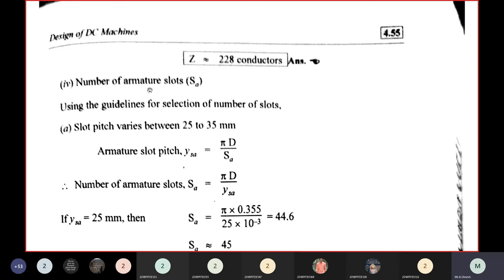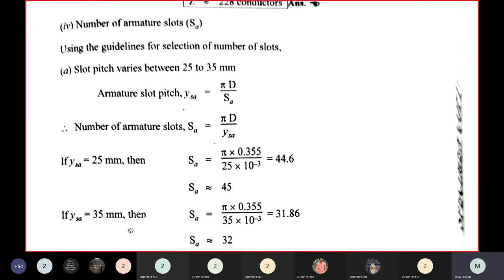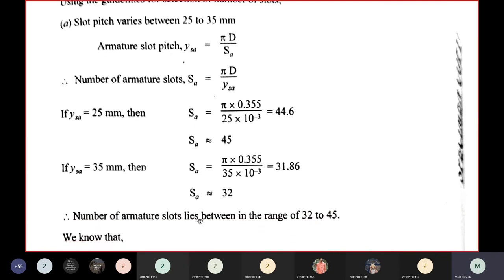Number of armature slots SA: slot pitch YSA = πD/SA. For YSA = 25 mm: SA = π×0.355/0.025 ≈ 44.6, rounded to 45. For YSA = 35 mm: SA ≈ 31.86, rounded to 32. So SA lies in the range 32 to 45.